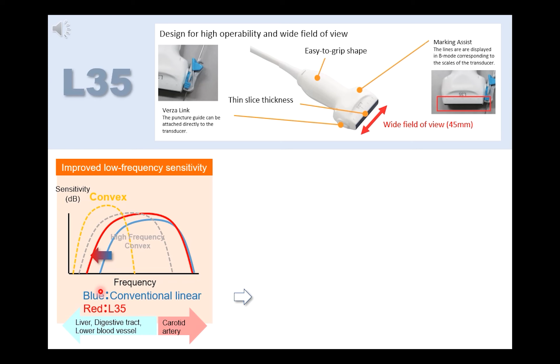So, L35 shifted its frequency bandwidth to the lower frequency side. The sensitivity of the probe is also improved by using a single crystal. This allows for high visibility and penetration to capture minute changes. The probe is widely applicable to abdomen, lower extremity veins, and carotid arteries.